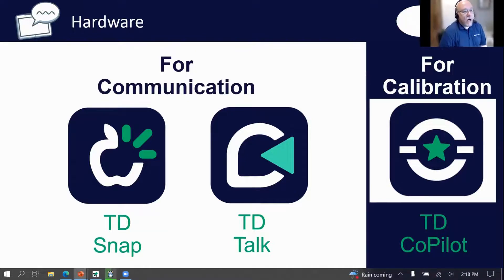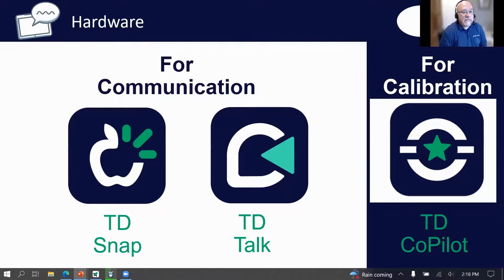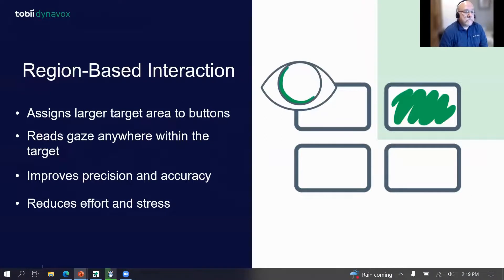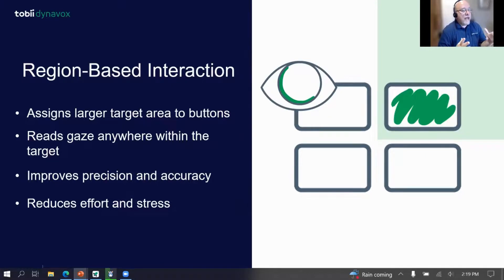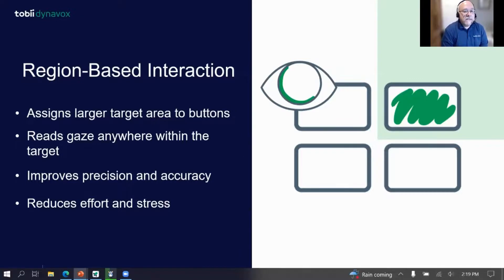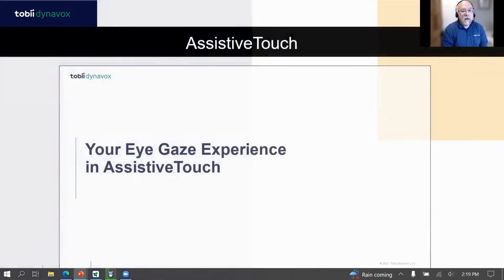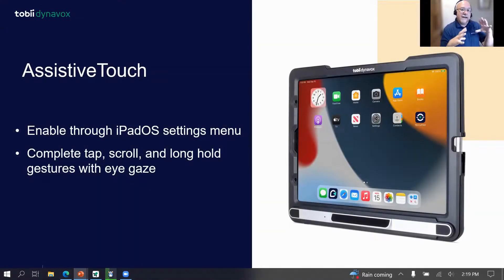TD Snap and TD Talk both come with the device, along with TD Copilot — our software that allows calibration and customization of the tracking settings for your needs. Our software has something called region-based interaction, where we assign larger target areas or buttons, and it allows your gaze to be read anywhere within that target area, helping with efficiency and access.